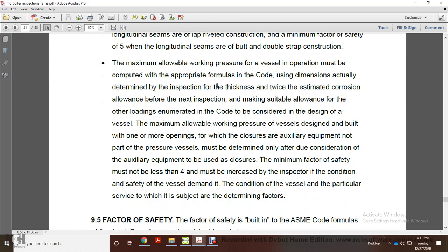Maximum allowable working pressure for a vessel in operation must be computed with the appropriate formulas of the code, using the actual dimensions determined at inspection, with thickness less twice the estimated corrosion allowance before the next inspection, and making suitable allowances for other loadings enumerated in the code to be considered for the design of the vessel. The maximum allowable working pressure of a vessel designed and built with one or more openings for the enclosure of auxiliary equipment not part of the pressure vessel is determined only after consideration of the auxiliary equipment to be used in the closure. The minimum factor of safety must not be less than 4, and must be increased by the inspector if the condition or safety of the vessel demands it.